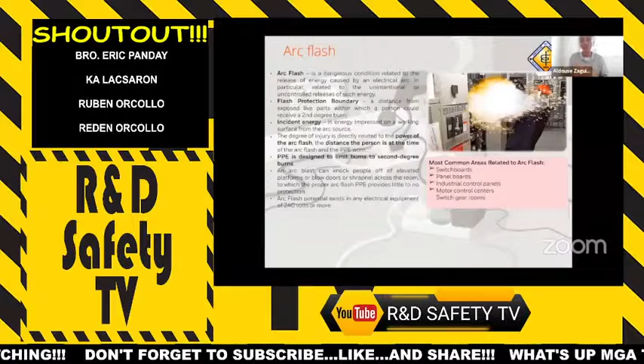In your own facilities, with your switchboards and switchgear, sometimes you draw boundary lines near the equipment pedestal. That line isn't drawn arbitrarily — you have to refer it to your Licensed Electrical Practitioner (LEP) to determine how far it should be placed. It's not just there for the sake of having a line, because if it's drawn incorrectly, say it's actually high voltage but the line is too short, it remains unsafe for people passing by the equipment.